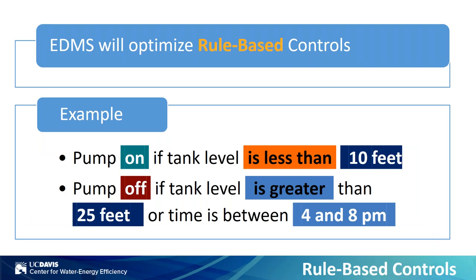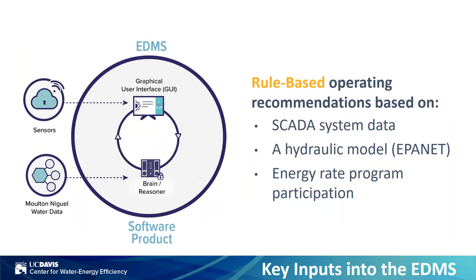So how are operators actually running their systems? They're typically managed using rule-based controls implemented in SCADA and overseen by operators, with day-to-day decisions made on top of that. The effects of these rule-based controls can be easily interpreted by operators, and they are very resilient to varying water customer demands. The EDMS focuses on optimizing these rule-based controls rather than fully relying on pump schedules. An example of a rule-based control would be to turn a pump on if a tank level is less than 10 feet, or to turn that same pump off if a tank level is greater than 25 feet or the time is between 4 and 8 p.m.